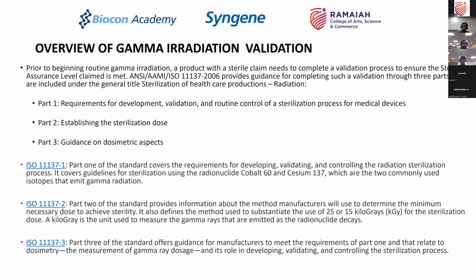It has three parts. Part one is titled Requirements for Development, Validation, and Routine Control of a Sterilization Process for Medical Devices. Part two is establishing the sterilization dose, and part three is the guidance on dosimetric aspects. So let's just understand what this is. Part one of the standard covers the requirements for developing, validating, and controlling the radiation sterilization process. So, how do we first of all control the radiation process, the sterilization process? How do we validate the process? This is what is covered in part one.